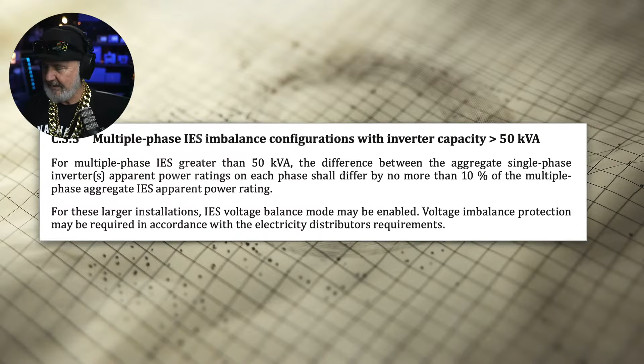Okay, so what have we got here? So connection of the IES, as I mentioned, it must be to a dedicated circuit. That's not new. We'll cover the requirements for selection of wiring systems, control and protection, isolation, interface protection. There's a new term. What used to be called secondary protection or grid protection is now referred to as interface protection. Well, what that means is where you interface with the DNSPs or the lines company's equipment, there may be rules around, and there's some default settings in this standard about the maximum size that you can have before you need to have a separate piece of equipment known as interface protection.